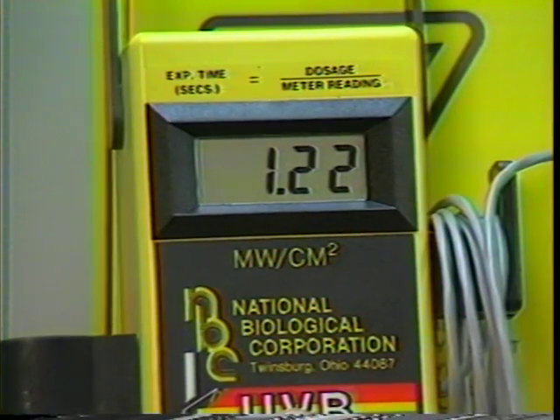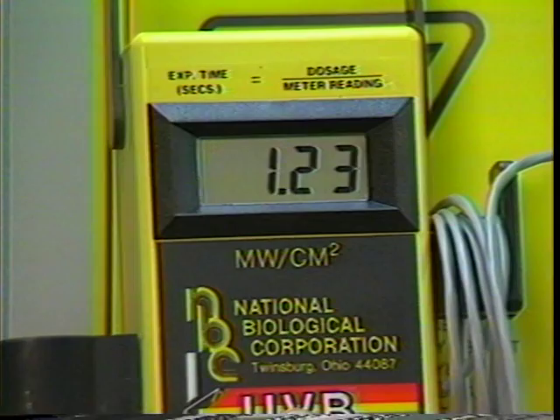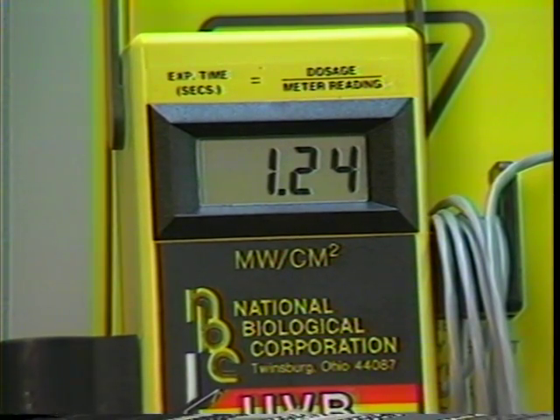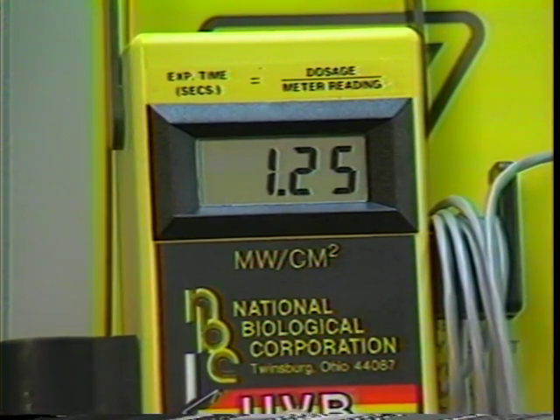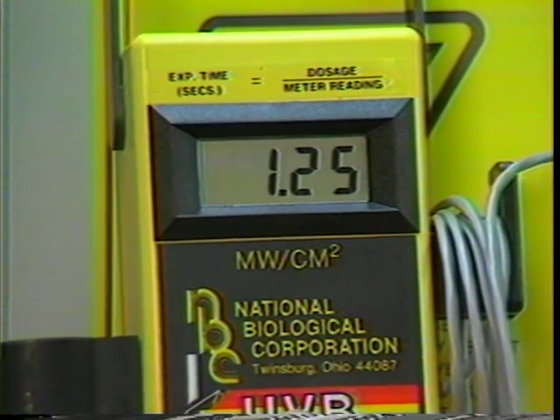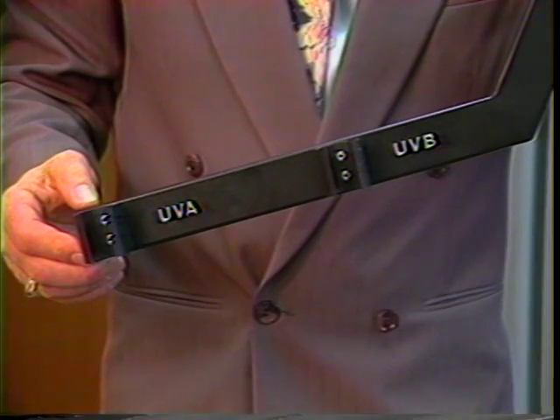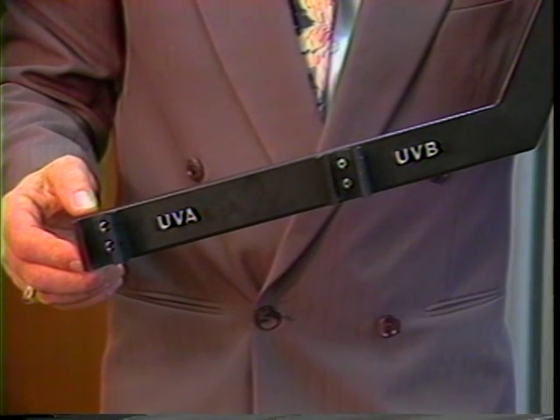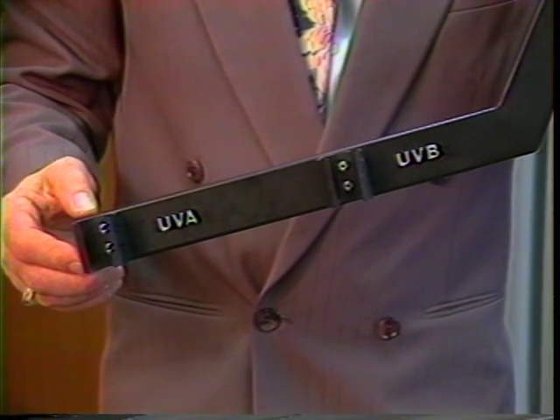Now depress the red button on the UVB meter and hold it down until a stable reading is obtained. Write that reading down in an easily accessible chart maintained daily. The above warm-up procedure and measurement output must be repeated for the UVA lamps. If you choose, you may turn both sets of lamps on at the same time when warming up. But care must be taken to place the UVA metering probe in the probe clip marked UVA at the end of the metering bar. The proper dosage information is the last requirement before patient treatment.